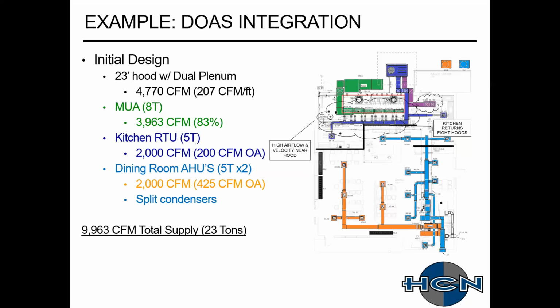So here's an example of the design we actually worked on in Tennessee. This is a 23-foot hood. You're exhausting about 4,800 CFM, with a dedicated makeup air unit with heating and cooling, 8 tons, a rooftop unit for that kitchen space. And then your dining room has a couple of air handling units with remote condensing units. So for this design, you're looking at almost 10,000 total CFM of supply, 23 tons.